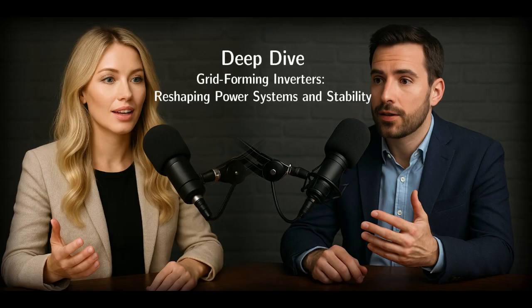So we're really talking about some major paradigm shifts, like moving from grid following to grid forming as the expectation for new renewables. They have to contribute to stability now. Exactly. And shifting from relying on mechanical inertia to utilizing electronic or synthetic inertia, it's faster, it's more flexible, but it behaves differently. Also, a shift from purely centralized control of stability to incorporating distributed control, with these grid-forming resources spread throughout the network. Yes, that decentralization is key. And finally, a shift in protection philosophy, moving from just reacting to faults to proactively coordinating with these intelligent devices to maintain stability and prevent cascading failures.